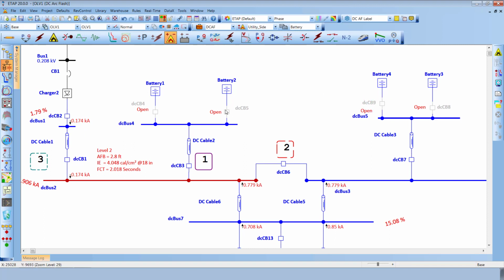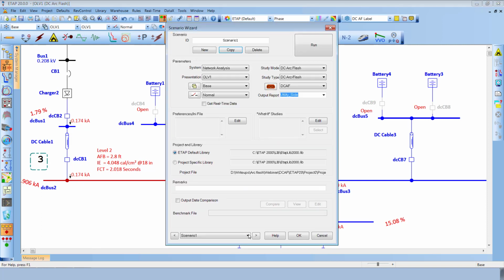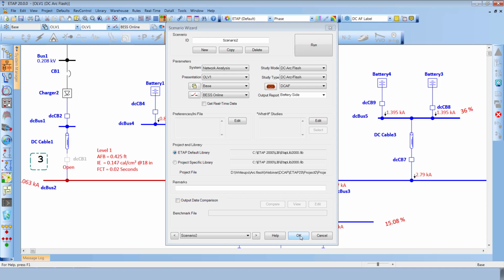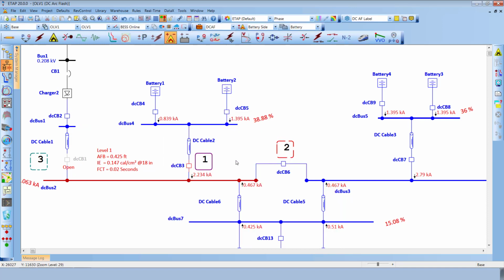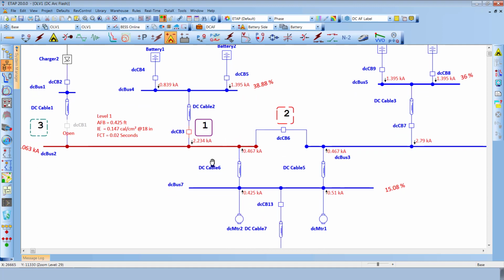Scenario number 2 actually deals with the loss of utility condition, where the contribution is primarily from the battery sources only. In this case, we do have protective devices that operate based on the actual sequence of the current seen by the protective device, and the trip time is calculated.